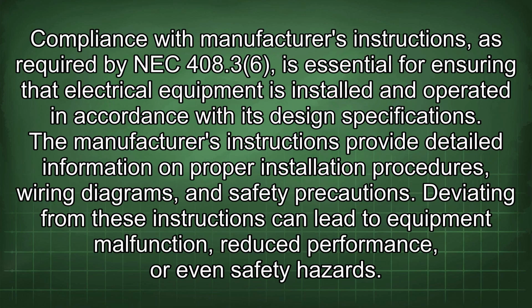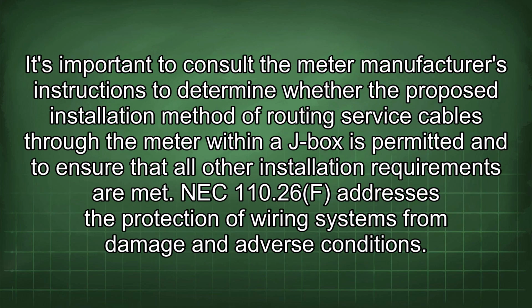Compliance with manufacturer's instructions, as required by NEC 408.3(6), is essential for ensuring that electrical equipment is installed and operated in accordance with its design specifications. The manufacturer's instructions provide detailed information on proper installation procedures, wiring diagrams, and safety precautions. Deviating from these instructions can lead to equipment malfunction, reduced performance, or even safety hazards. It's important to consult the meter manufacturer's instructions to determine whether the proposed installation method of routing service cables through the meter within a J-box is permitted, and to ensure that all other installation requirements are met.